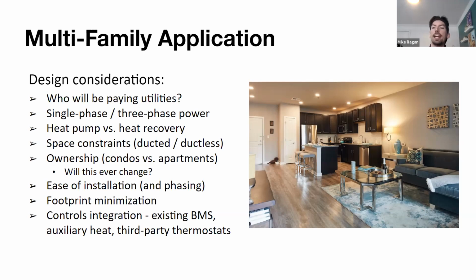Footprint minimization. Do we have limited space on the rooftop? Or if it's a high rise, for example, we don't really have a lot of footprint there. If the building owner wants to incorporate a solar PV array into their building, it's going on the roof and they don't have any space for condensing units. That's fine. That's perfectly fine. But that's definitely going to force our hand one way or another. Potentially, we may look at mounting split equipment on the side of the building, because it's much smaller, has less weight requirements, and we can mount everything on the side of a building, especially if it's out of sight of any roadway or common walk paths, if aesthetics are an issue.